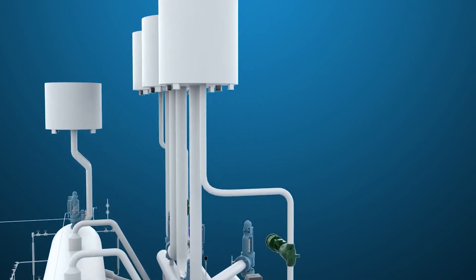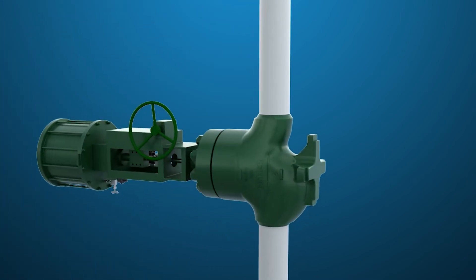While there is generally an isolation valve upstream of the control valve, it is important for the sky vent valves to shut off tightly in the event there are issues with the isolation valve.